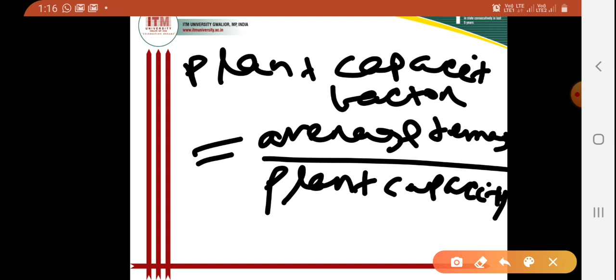If I want to talk about our annual plant capacity factor, I can write here that it means the total energy consumed or generated in a year, that is the annual output in kilowatt hour, divided by the plant capacity into the number of hours in a year, that is 8760 hours. So this is our plant capacity factor.